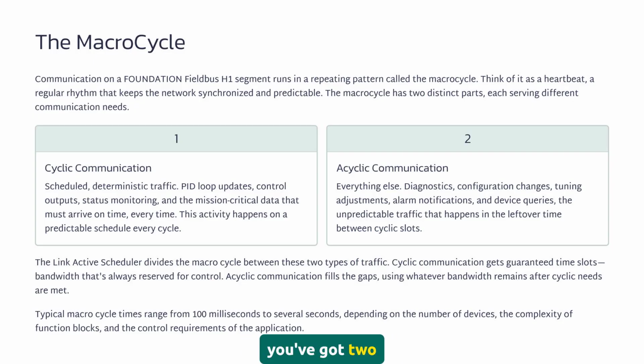Every cycle you've got two parts, cyclic and acyclic. Cyclic is the scheduled deterministic stuff. That PID loop we just talked about, cyclic. Your pump status updates, cyclic. It happens on a predictable schedule. You know it's going to happen every 50 milliseconds or every 100 milliseconds, whatever you configured. Acyclic is everything else. Diagnostics, configuration changes, parameter uploads, tuning adjustments, non-critical data.